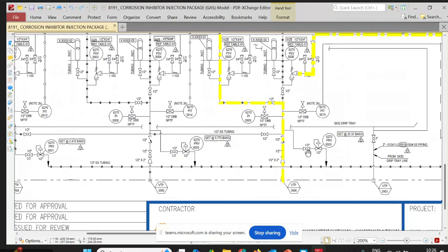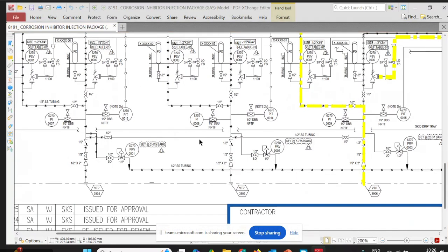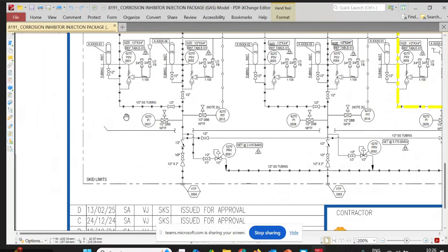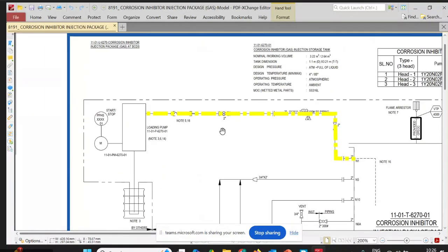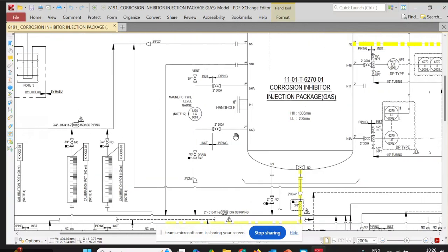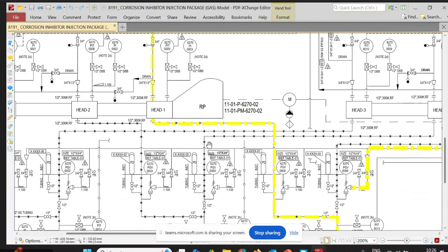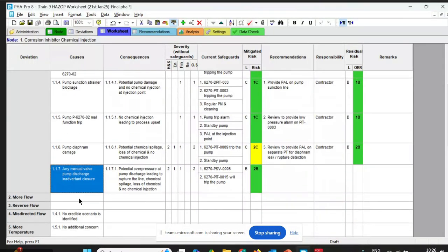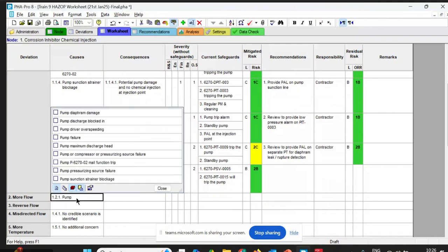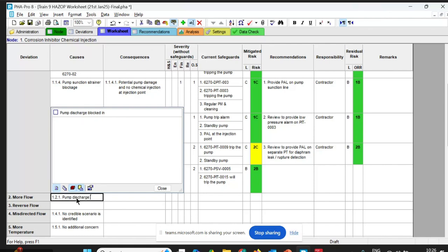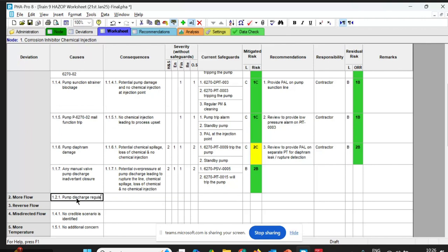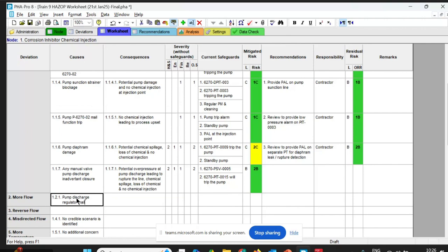Now for no flow, we have seen. Now we'll go for more flow. The more flow case here is not a credible scenario. What about the regulator? Because we have a regulator at each pump discharge line. So regulator malfunction, then you can say. We can say regulator malfunction, yes, right. More flow, regulator malfunction. Pump stroke. What do you say, regulator? What is the right word? Pump discharge. Misadjustment of the stroke of the pump. Yes, you are right.